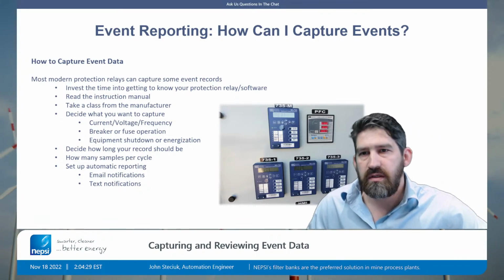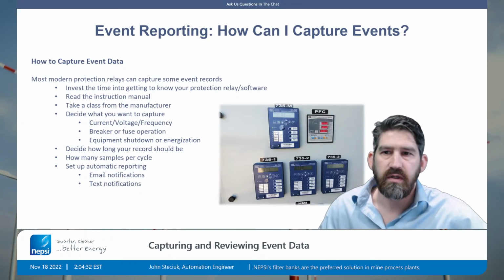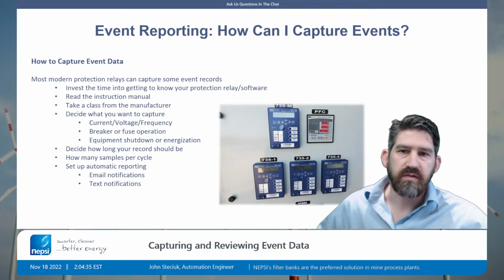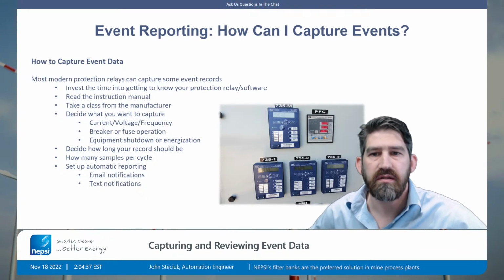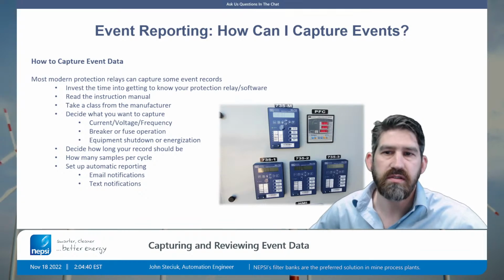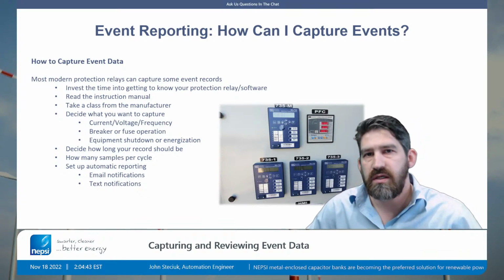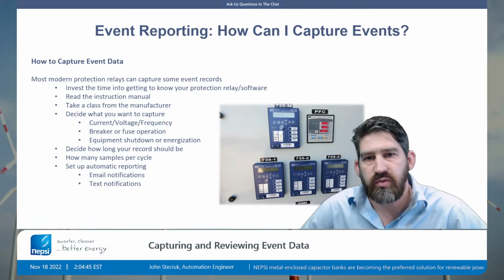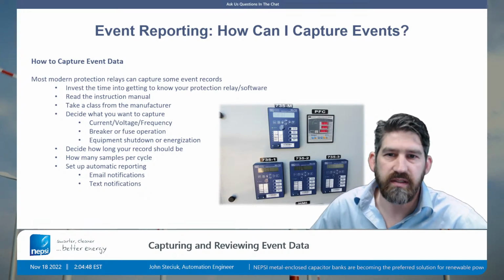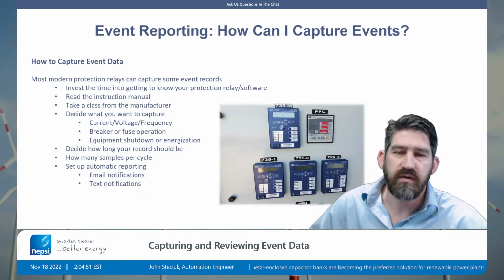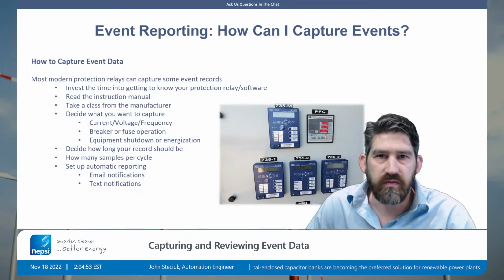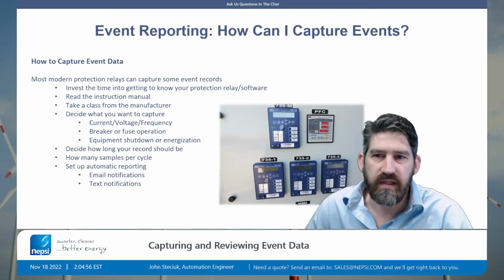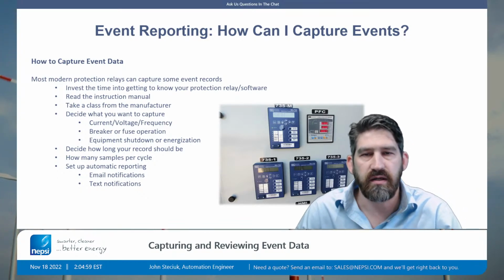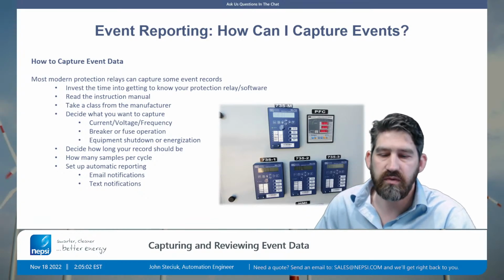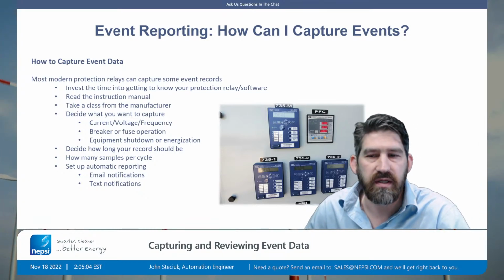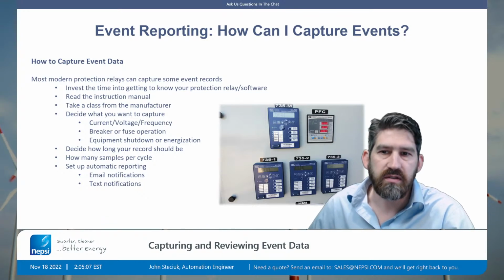Alright, so how can we capture event data? Well, most modern protection relays have the capability of capturing some type of event records, and it's really important to get to know the protection relays that are used at your plant, get to know the software and how to set it. A good way to do that is to read the instruction manual. I always find that any relay that's worth its weight will have a very thorough instruction manual, and it will describe all the capabilities and how to use the relay. So that's a good starting point.